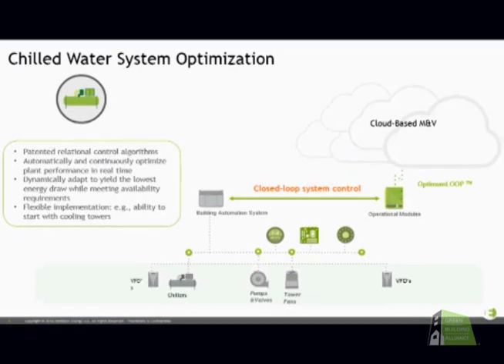You want to have the option, and that's why we show a cloud-based M&V, measurement and verification. So you're able to look at if there's any changes in your system. Traditionally you've had a chiller that operates at 0.6 kW per ton, and all of a sudden for the last week you can see it's been at 1 kW per ton. You're alerted to the fact that there's some sort of an issue, something needs to be corrected.